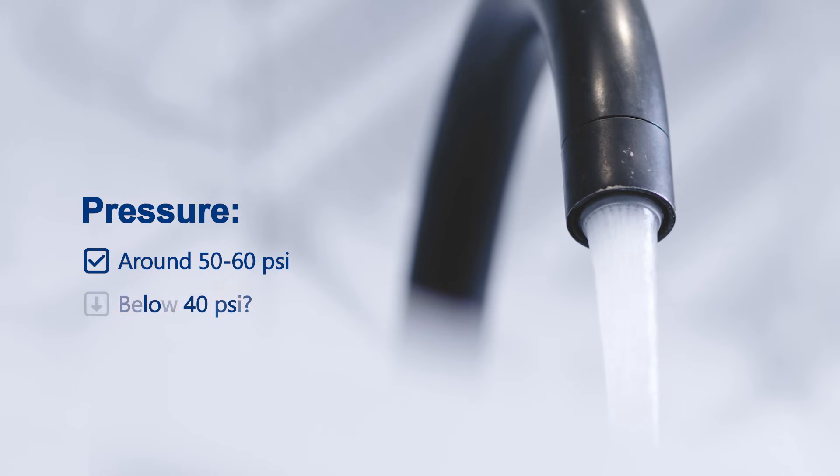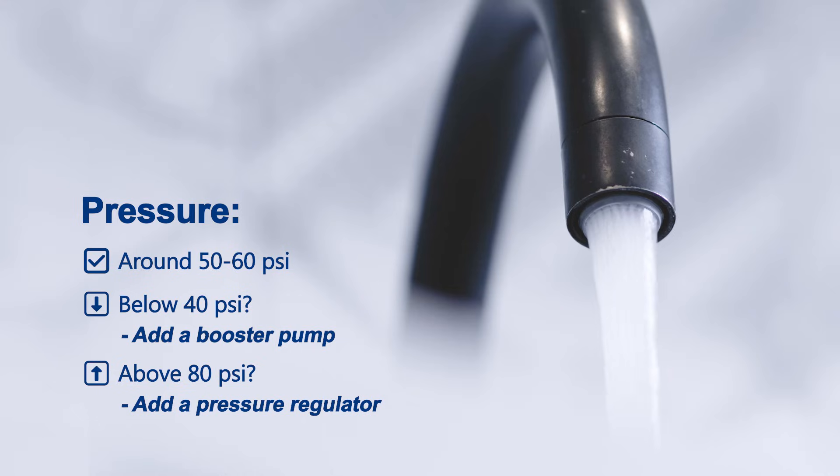If you are operating below 40 psi, add a booster pump. And if you're above 80, add a pressure regulator or feed water tubing of the RO system.